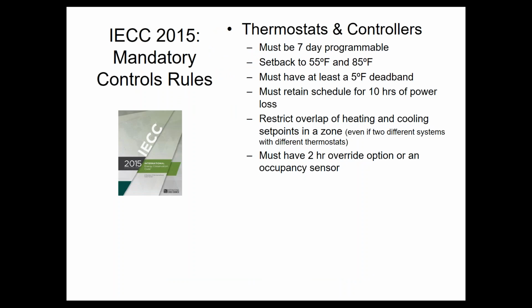All right, regarding control stuff, I'm going to touch on a couple things, and then the rest of the control stuff we're going to save for next week. But just like with residential, you got to have programmable stats. In the case of a commercial project, they have to be 7-day programmable. You got to have at least a 5-degree deadband between the heating and cooling. So if your heating set point is 70, you cannot have a cooling set point any lower than 75, right? That kind of thing. You can't have overlapping heating and cooling set points.